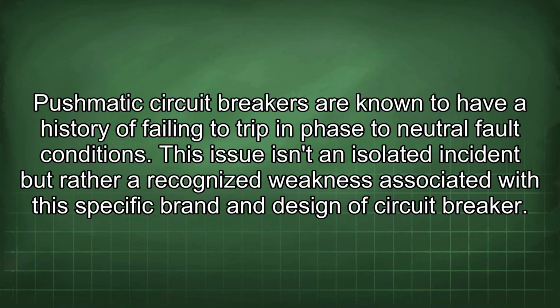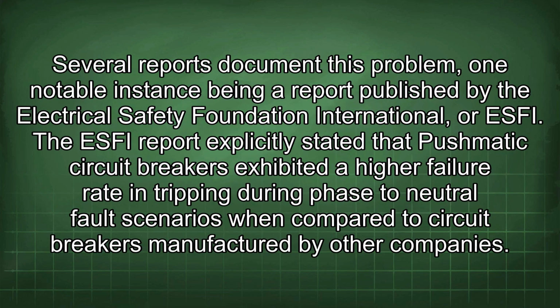Pushmatic circuit breakers are known to have a history of failing to trip in phase-to-neutral fault conditions. This issue isn't an isolated incident, but rather a recognized weakness associated with the specific brand and design of circuit breaker. Several reports document this problem, one notable instance being a report published by the Electrical Safety Foundation International, or ESFI. The ESFI report explicitly stated that Pushmatic circuit breakers exhibited a higher failure rate in tripping during phase-to-neutral fault scenarios when compared to circuit breakers manufactured by other companies.